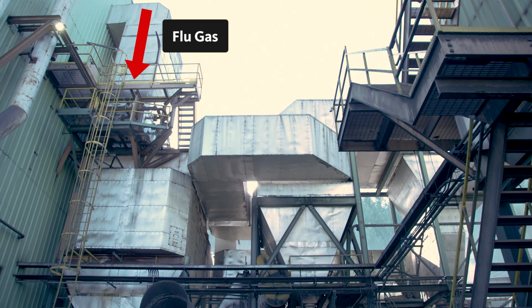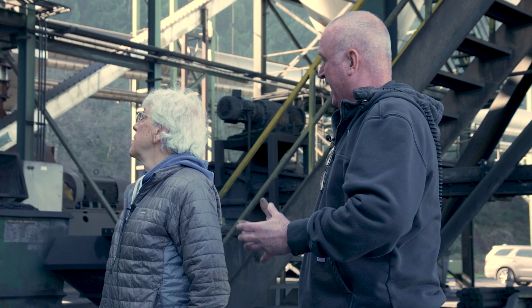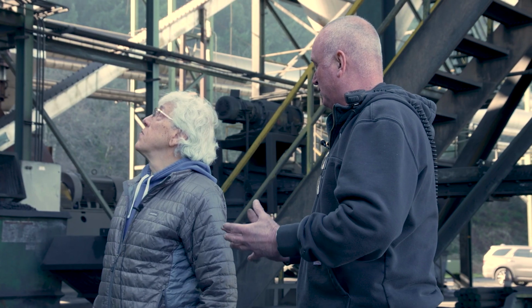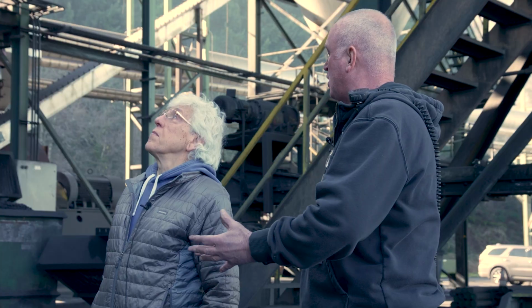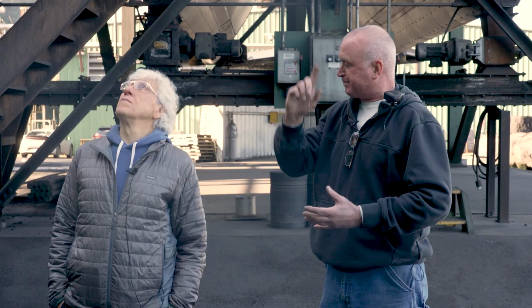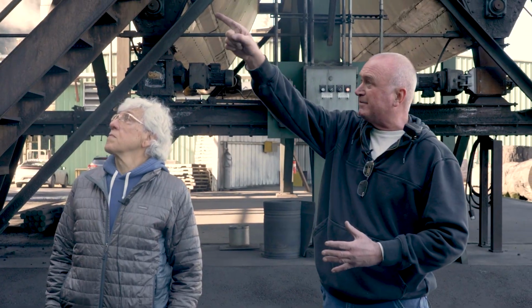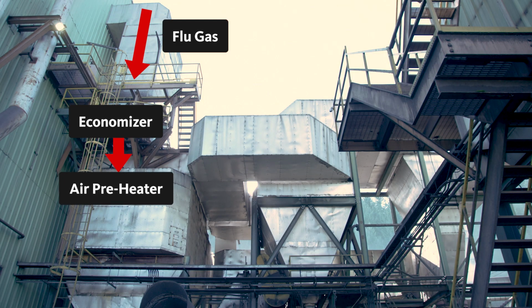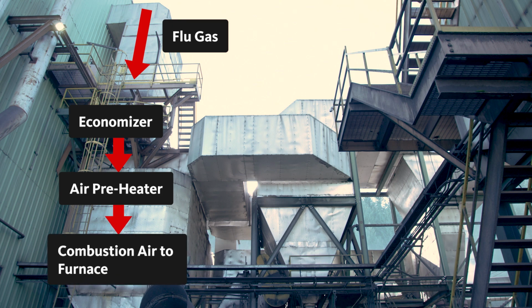It comes down to what we call an economizer. So the idea is to take every bit of latent heat we can out of that flue gas. We want to get all of it. Yeah. So we preheat what we call feed water before we send it to the boiler with the latent heat of that flue gas. It then travels down into an air preheater where we use the latent heat of that flue gas to heat up the combustion air prior to going under the grate rolls for the combustion process.